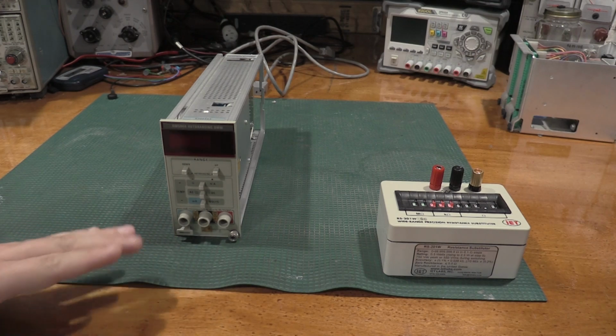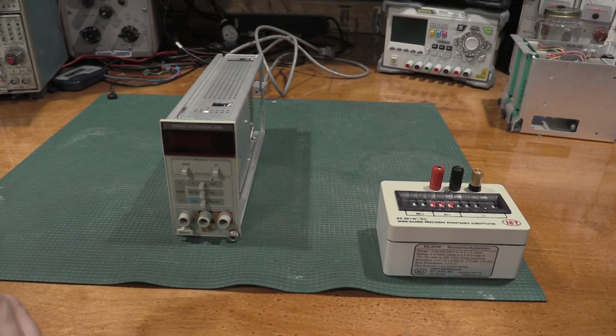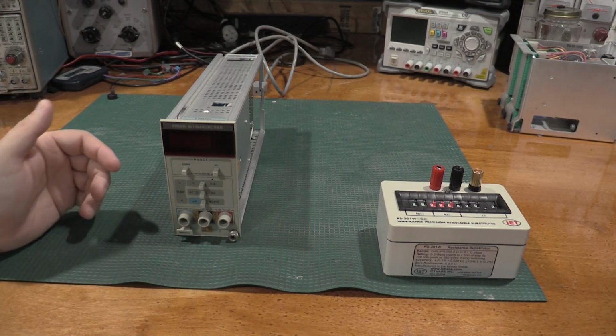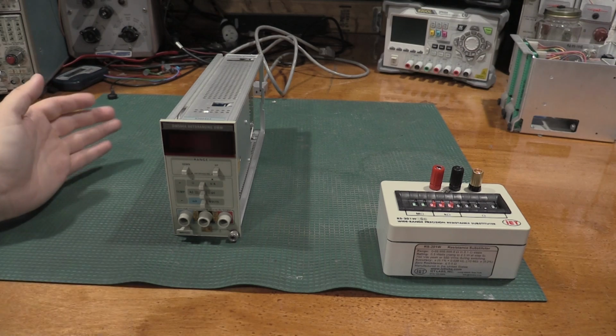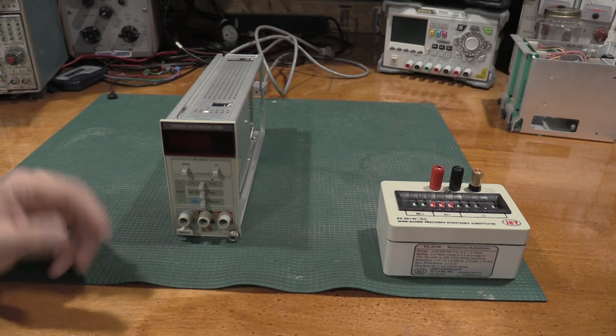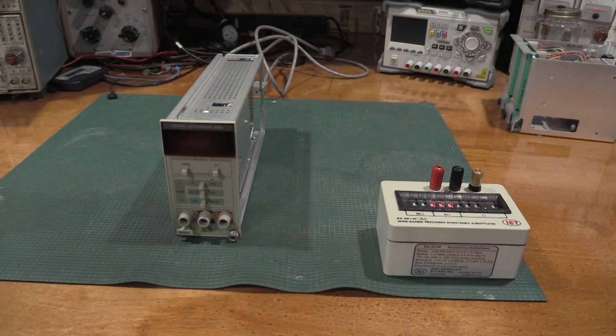But what ends up happening is, when you send a device out for calibration, that's not calibration, alignment, and repair. That's just calibration. All they're going to do is check all the ranges, check all the functions. As long as it meets the spec sheet, it is now, quote, calibrated, and they send it back, which essentially says the device meets spec, everything's good. It could get kicked back failed, where it's broken and needs to be repaired, which is one of the reasons why we have the Cal Lab here in the lab, due to doing some of the scopes and some of the older pieces of equipment.